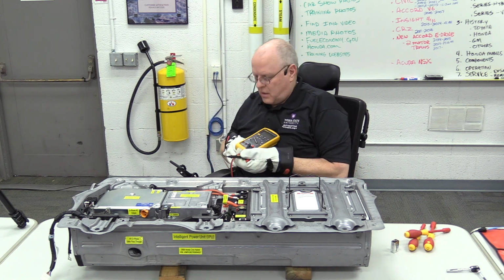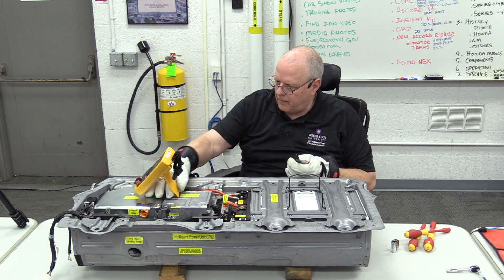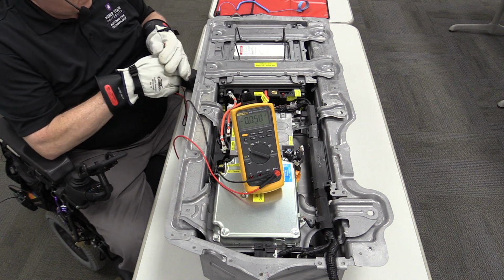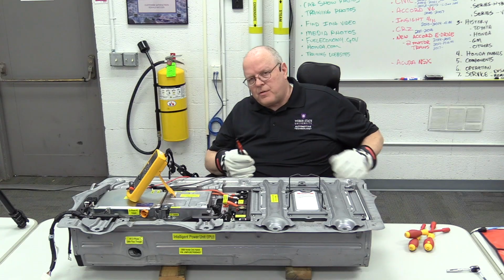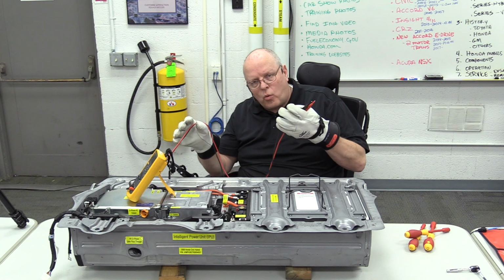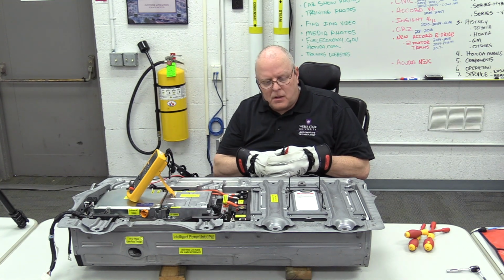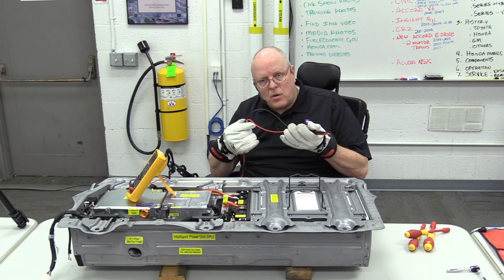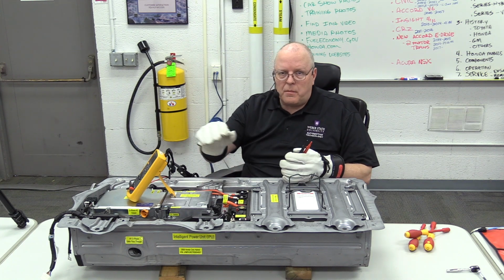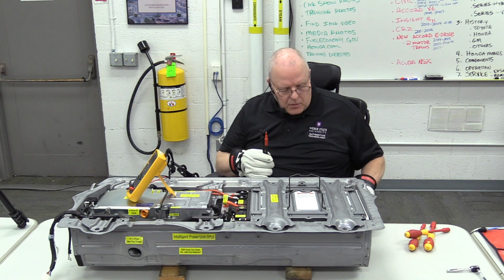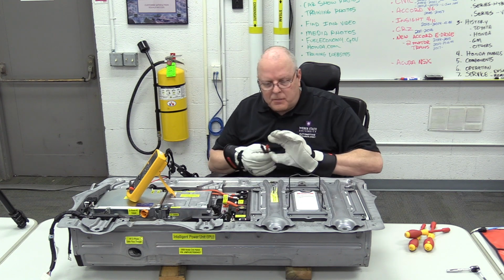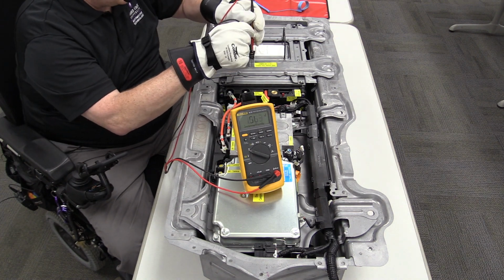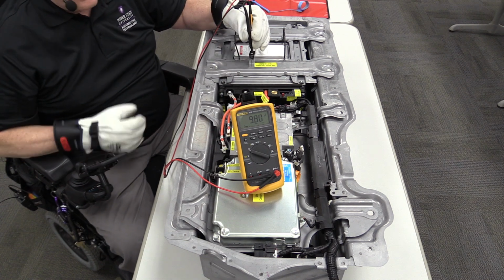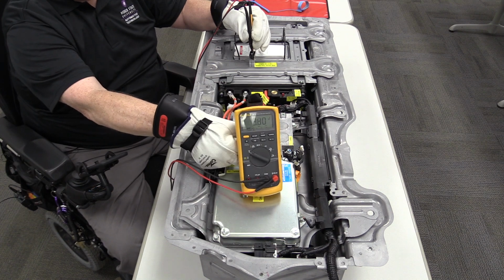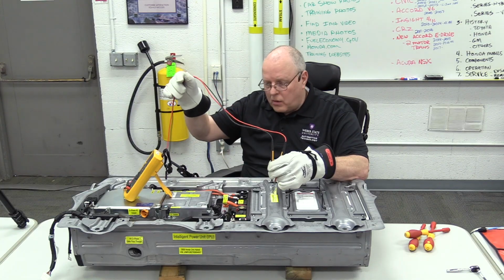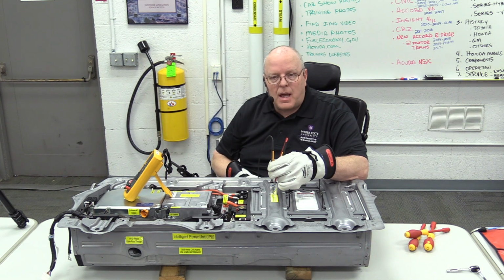I'm going to turn our multimeter to DC volts. I had a viewer here on YouTube comment that in my previous video I did not test the meter and the meter leads to see if they even worked before doing measurements on high voltage systems, and he's absolutely right. We could have a broken meter lead internally, which has happened over the years. These Fluke meters are great, but the leads can sometimes go open with continuous use. So I've got a little 9-volt battery right here, and I'm just going to put the meter leads across that and see if we read battery voltage. I've got 9.8 volts right there, which tells me the meter leads are not open, they're working properly, and the meter is capable of reading a voltage.